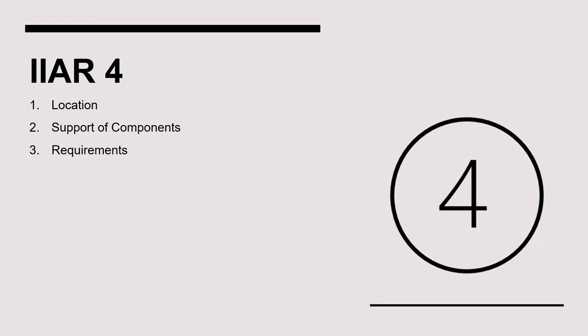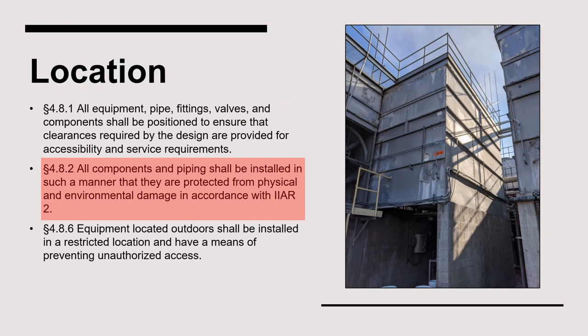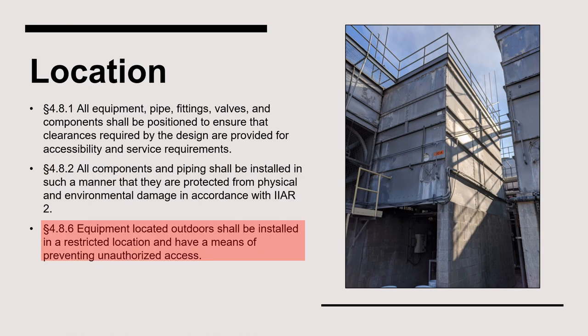Moving on, we'll dig into the condenser installation requirements in IIAR Standard 4. Section 4.8 requires that all equipment be positioned to ensure clearance is provided for accessibility and service requirements. Furthermore, the condenser must be protected from both physical and environmental damage. When installed outdoors, equipment must be in a restricted location and have a means of preventing unauthorized access.